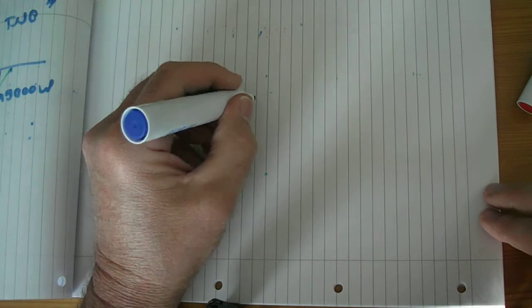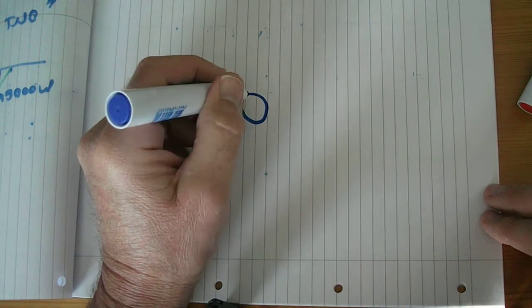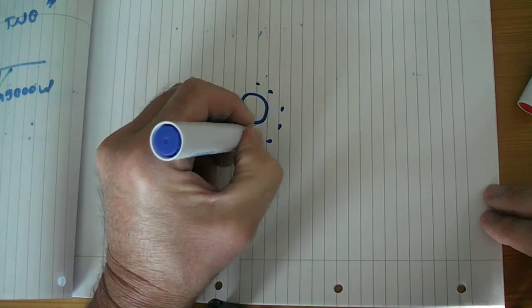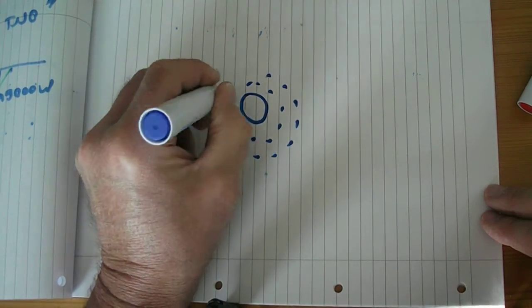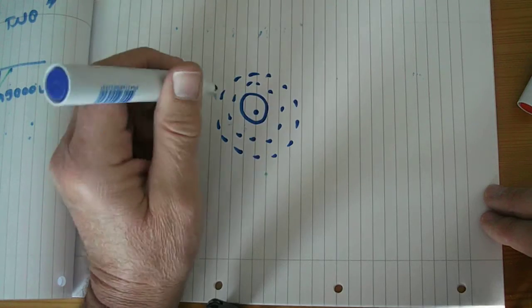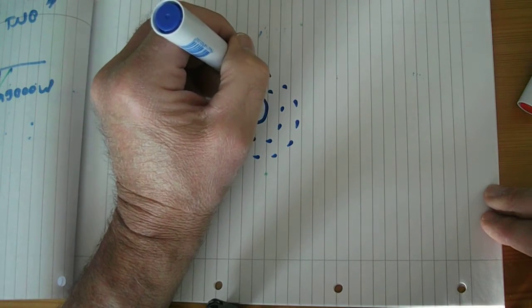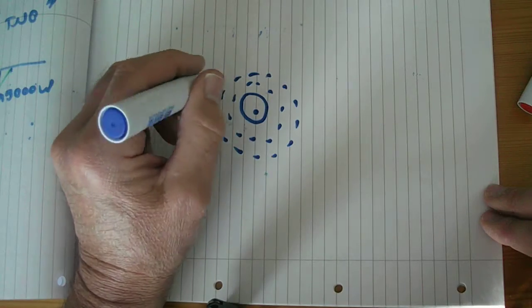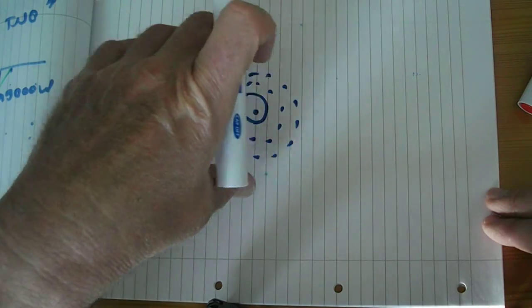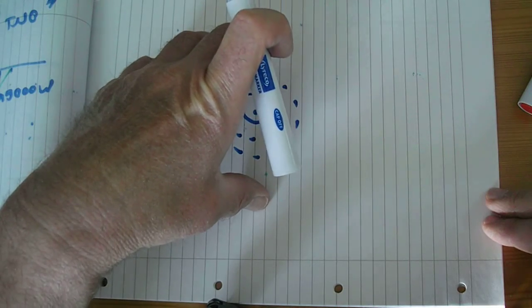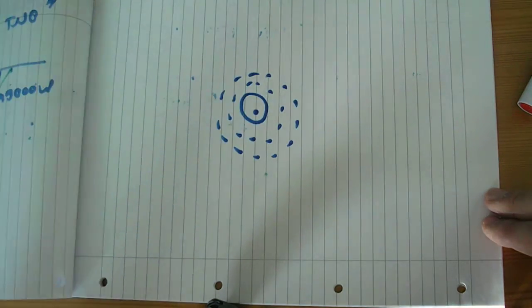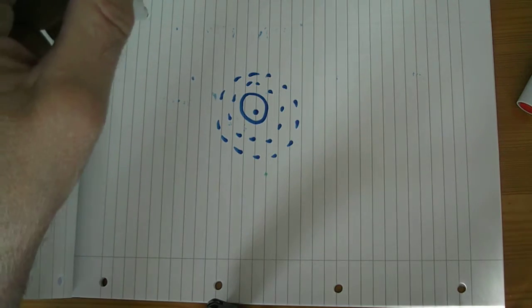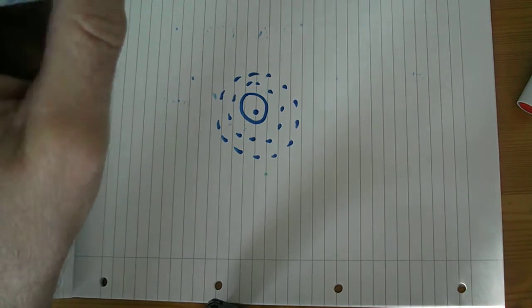I put quite a good video up by somebody else who did one on corona discharge. And when you have an overhead line, the electric field produced by the current going backwards and forwards in that conductor can cause ionization of the air particles, and what that causes is a sort of visible glow and a hissing and buzzing sound. But because it's all along the line, it can also increase your power losses in the line.